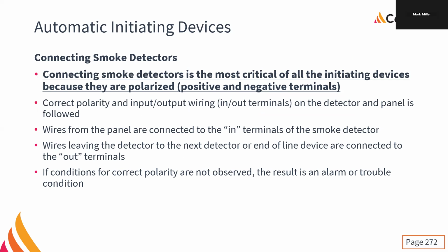Wiring is critically important because this is the first time we're dealing with a polarity sensitive device. Positive and negative matters. They're also directionally sensitive the vast majority of the time. So the in and out matters: putting the wires from the panel to the in and then out to the next device. And that matters.